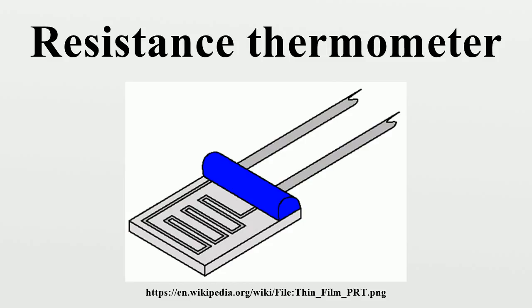Lead wire. Errors that occur because a 4-wire or 3-wire measurement is not used. This is greatly increased by higher gauge wire. 2-wire connection adds lead resistance in series with the PRT element. 3-wire connection relies on all 3 leads having equal resistance. Self-heating. Error produced by the heating of the PRT element due to the power applied. Time response. Errors are produced during temperature transients because the PRT cannot respond to changes fast enough. Thermal EMF. Thermal EMF errors are produced by the EMF adding to or subtracting from the applied sensing voltage, primarily in DC systems.